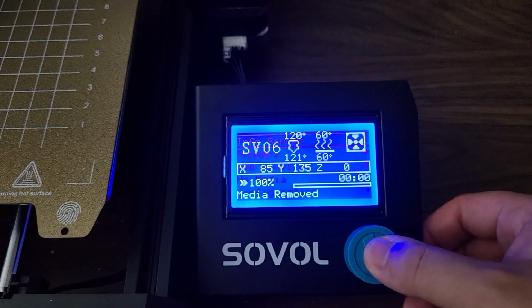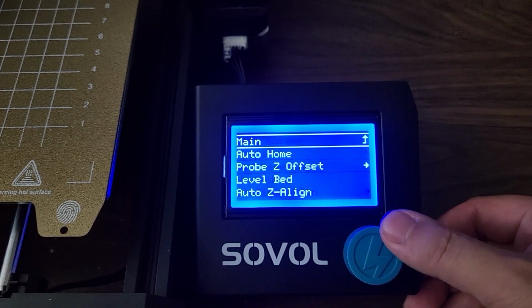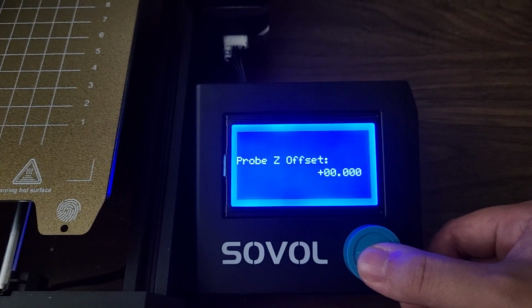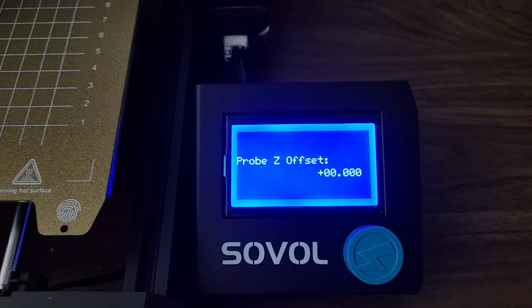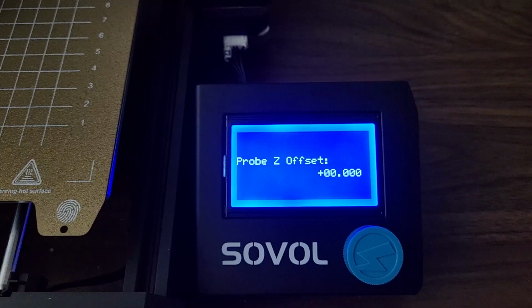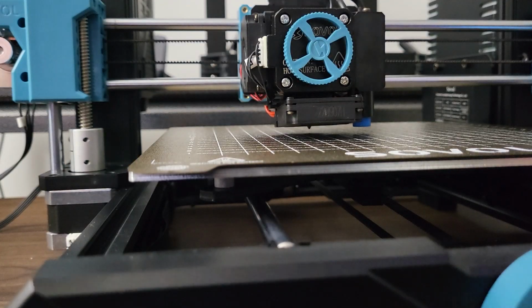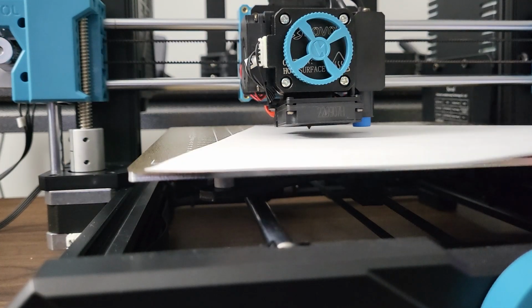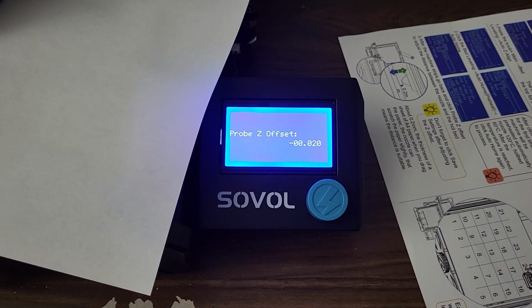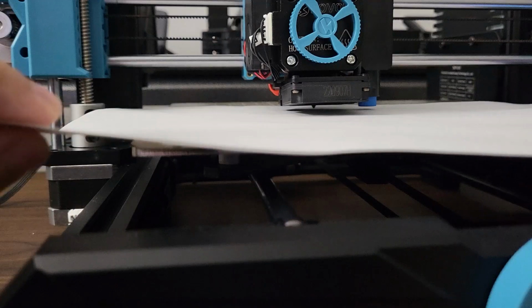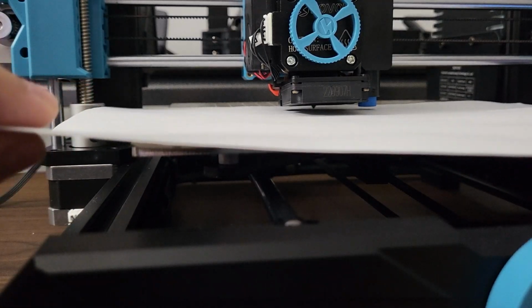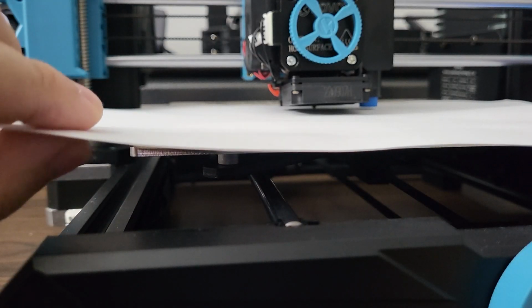Now we can select bed leveling, probe Z offset. It allows you to set the compensation for the Z axis. Take an A4 paper and place it under the nozzle. Slowly adjust the knob counterclockwise to set a negative Z offset and move the nozzle closer to the bed. You'll feel some friction as it gets closer to the bed.